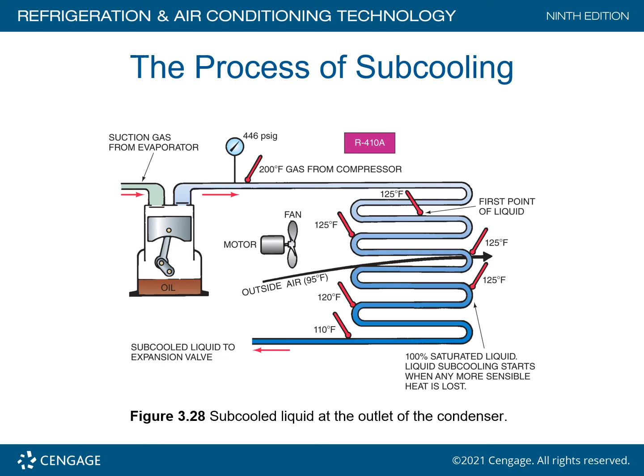And as you can see, it travels in these U-shaped bends. Notice that the temperature stays the same until it gets to about three-quarters of the way down. Now the temperature drops off to 120 degrees Fahrenheit. And then when it leaves the condenser, notice that the temperature drops when it's fully liquid, at 110 degrees. At this point, we now have subcooled liquid. And this subcooled liquid ensures that the metering device has no liquid-vapor mixture. It is a solid column of liquid. You want a solid column of liquid refrigerant, because if you don't have that, you're going to have problems with the refrigerant being able to pick up the heat in the evaporator. So the saturated liquid starts about right up here, and once we leave the condenser, we should have liquid and liquid only.